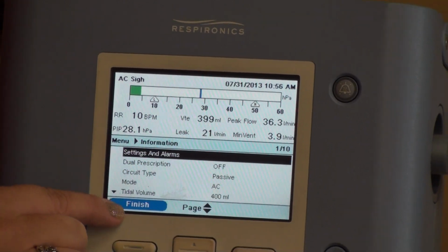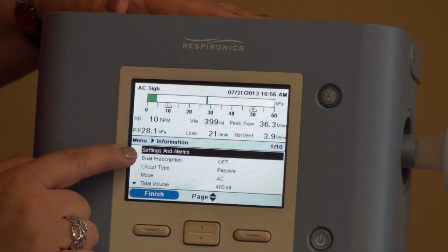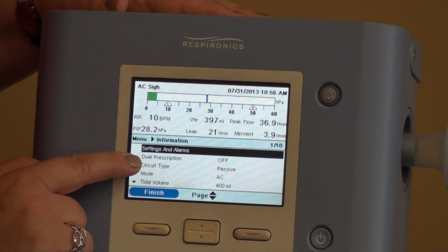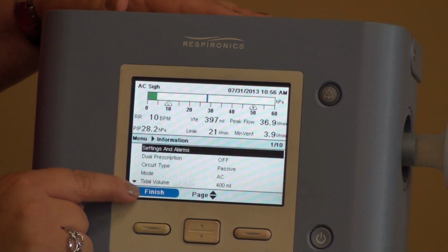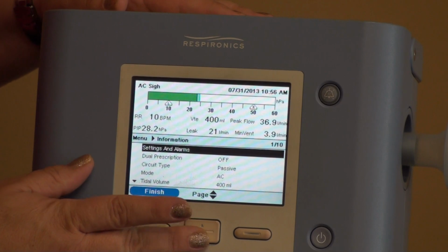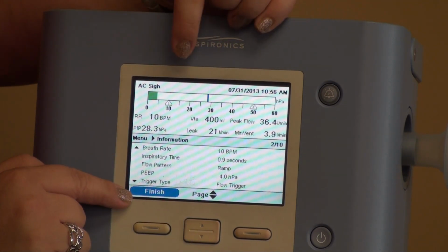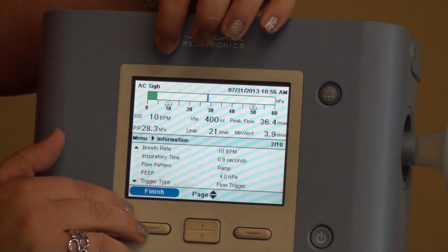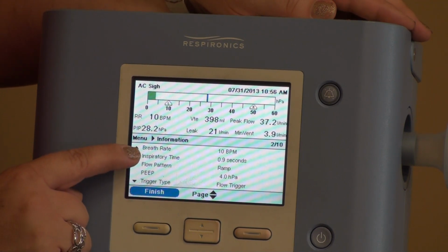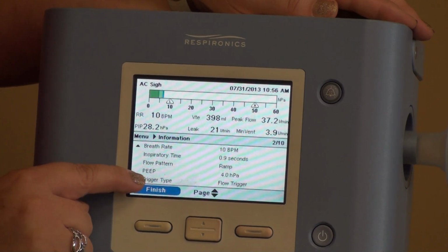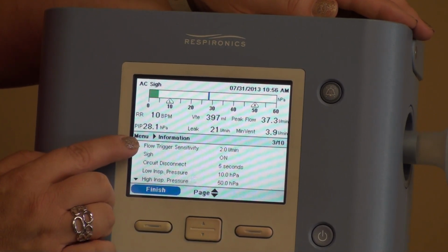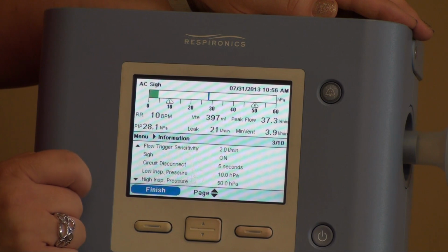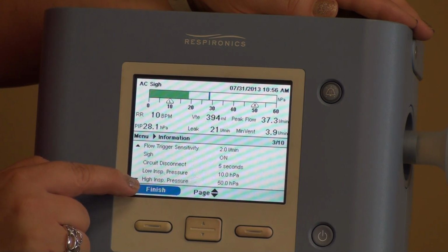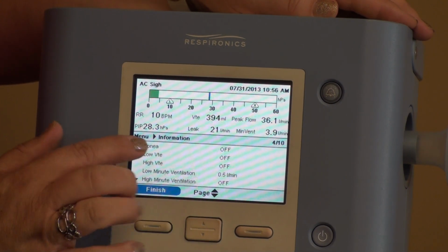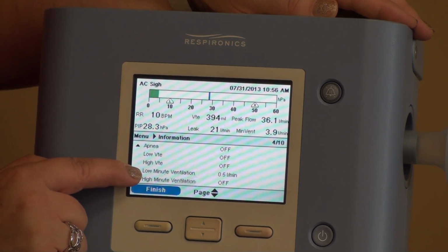And then that's where it's going to come up and you're going to see your settings and alarms. Your dual prescription is off. Your circuit type is passive. Your mode is assist control. Your tidal volume is 400. I toggle down. This is the only parameter place that it'll go down page by page. Breath rate is 10. Inspiratory time is 0.9. Flow pattern is ramp. PEEP is 4, flow trigger is what it's on. My sensitivity is 2, my Sigh is turned on. I have my low inspiratory pressure, my high pressure. And then down here on page 4, I have my low minute ventilation.